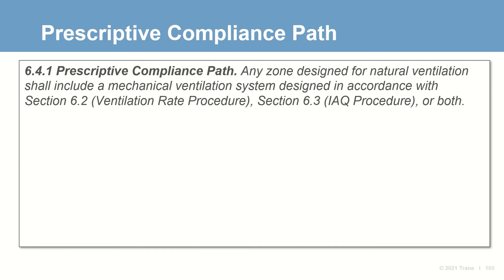When using the prescriptive compliance path, any zone designed for natural ventilation must also include a mechanical ventilation system designed using either the ventilation rate procedure or the IAQ procedure. This is often called a mixed-mode ventilation approach. When the natural ventilation openings are closed due to outdoor conditions or occupant preference, the mechanical ventilation system is activated to properly ventilate the zone.